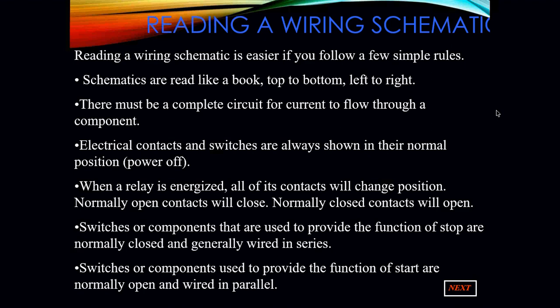One thing to always remember when you are dealing with reading a schematic, all of our switches, all of our safeties, stuff like that will be wired in series, one right after another with a load, a power consuming device. Our loads will be wired in parallel. That is really the breakdown of how to read a wiring schematic. You always start just like a book from top to bottom and you read each line left to right.